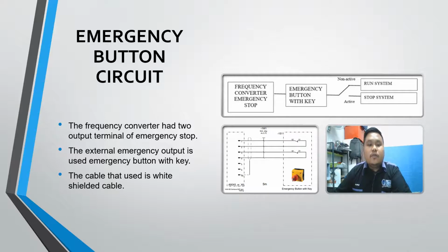Now, I would like to explain about the block diagram. In the block diagram, there are three parts. First, frequency converter. Second, emergency button with key. Third, system. The frequency converter will connect to the control box that is located in the control room. The connection between the control box and the frequency converter uses a white shielded cable. The emergency button will connect to the control box and the system. When the emergency button is active, the frequency converter system cannot be run, and it isolates the power connection from the frequency converter. But when the emergency button is not active, the system will run as usual.